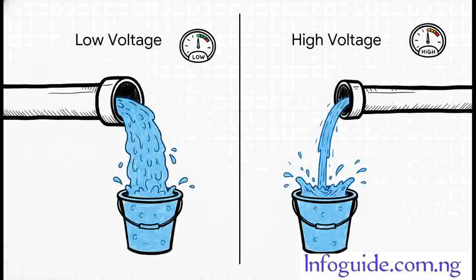Now this is where things get a little counterintuitive. You'd think a higher voltage system would need thicker wires, right? Nope, it's actually the opposite. A lower voltage system, like a 12-volt setup, needs thicker cables than a high-voltage 48-volt system. Why? To deliver the same amount of power, that 12-volt system has to push a much higher current, and higher current always demands a thicker wire.